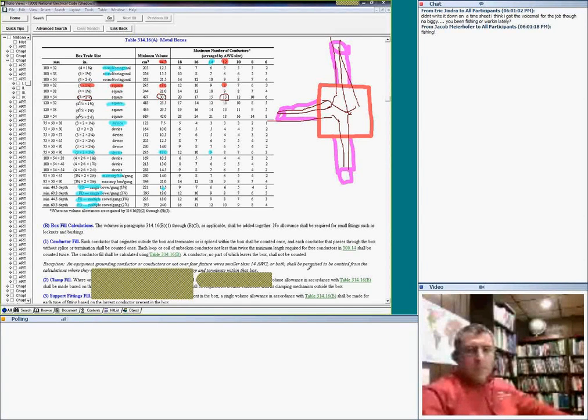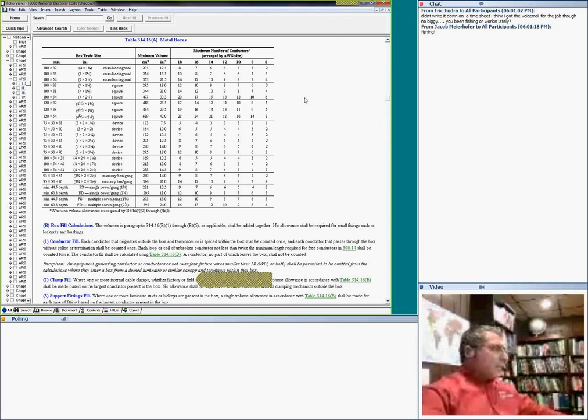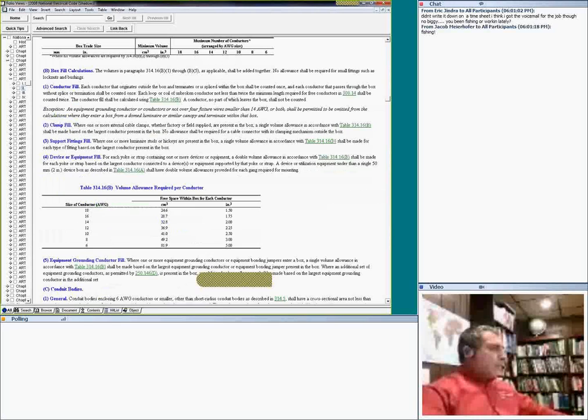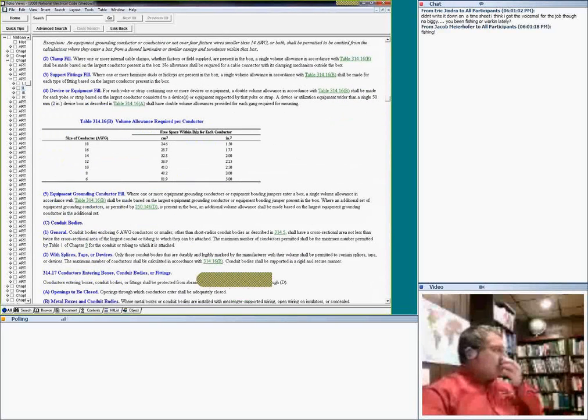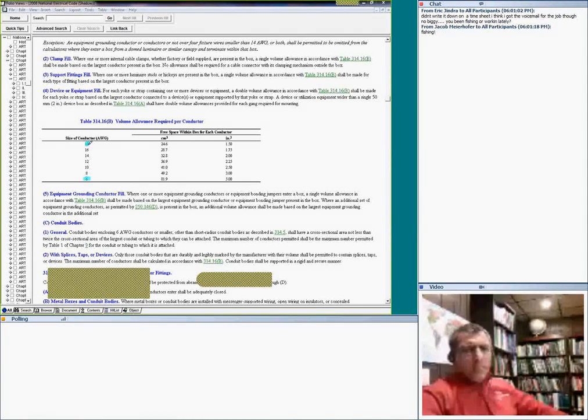And moving into, so this is table 1, guys. You don't go to town without knowing how to use it. We're going to table number 2, which you also can't go to town without using. Yeah? Table number 2, this is what I personally call the fuzzy math, being an engineer. They allocate a cubic inch for every type of conductor up to 6. For every conductor up to 6, from all to 18. And someone might say, Chad, what the heck with the 18?